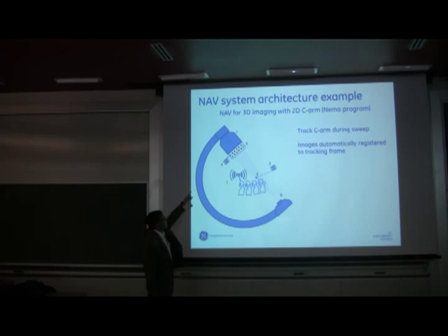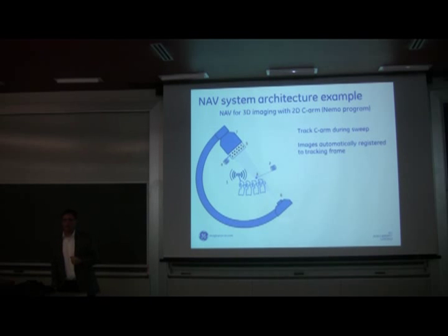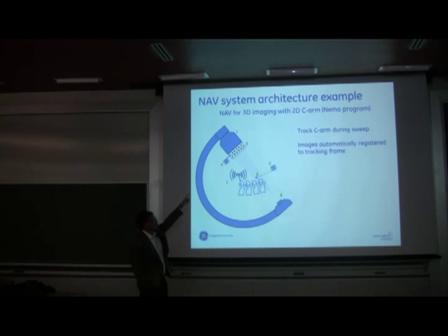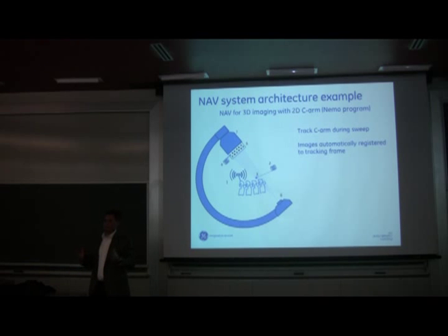The second thing is that the image detector depicted up here is actually an old image intensifier, which is basically electron optics, very sensitive to distortions from the Earth's magnetic field. They have a spherical input surface, so there's a pincushion distortion to the image itself. So we have an array of fiducial markers, or reseau marks, just as they used in the Voyager missions. The Voyager missions used a similar technology to linearize the images that came back digitally of the moons of the Saturnian system. So it's the exact same technology deployed on today's medical devices.